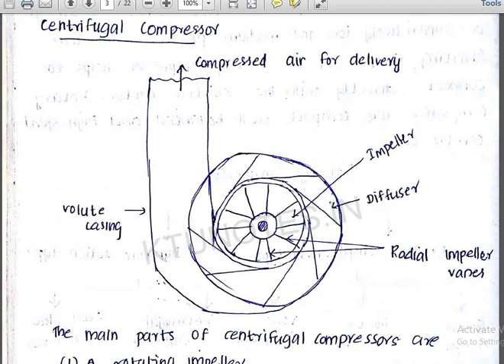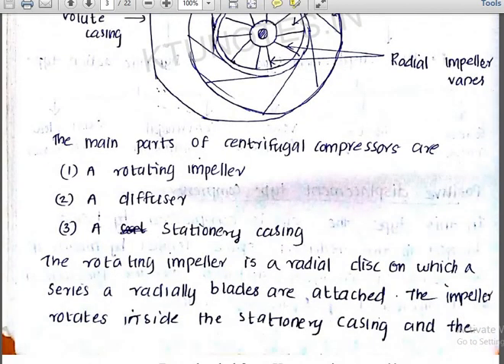The fluid then comes to a diffuser, which is a diverging area. According to Bernoulli's principle, the high kinetic energy is converted — the velocity head converts to pressure energy. This gives a high pressure at the outlet of the compressor. The centrifugal compressor consists of a rotating impeller, a diffuser, and a stationary casing — these are the main parts.